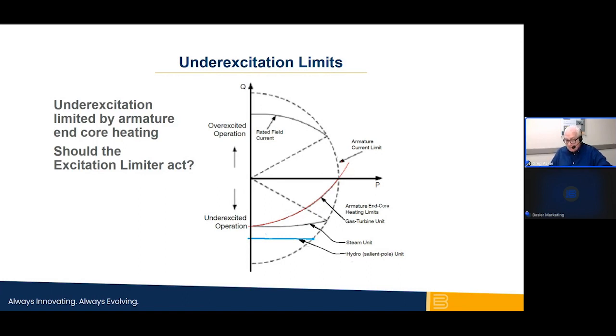The documentation will, as regular practice, depict three curves for the underexcited operation limits based on these three limiting conditions: loss of synchronism, stability limit, SSL, and the end-core heating limit, often a partial arc. Again, that's active near the maximum power output.